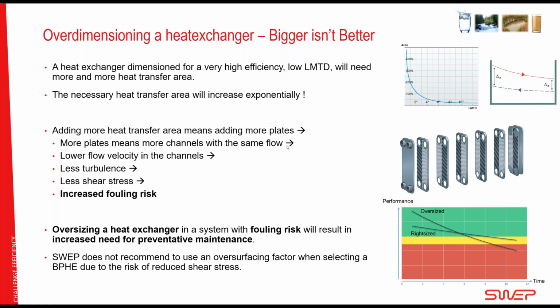So what will that mean? Adding more heat transfer area means adding more plates. And keep your eyes in this corner here. So when we add plates, what happens then? Well, we will have more channels, right? But we will have the same flow, and everything else is the same. But if we have more plates, more channels, and the same flow, we will have lower flow velocity, right? Lower flow velocity will have less turbulence, and less turbulence is less shear stress, and that's increased fouling risk.